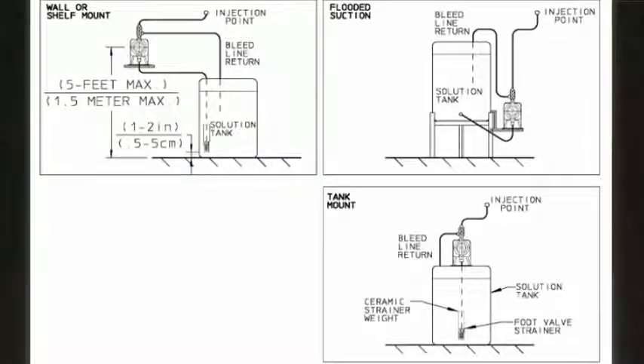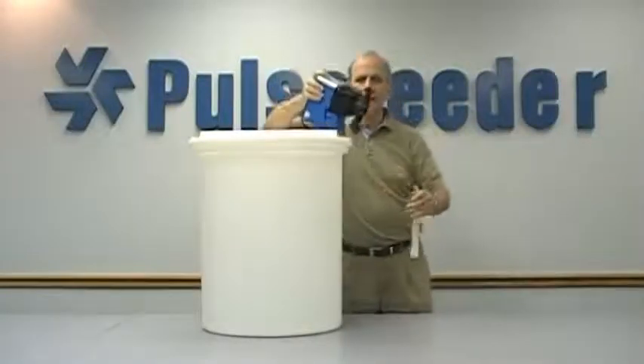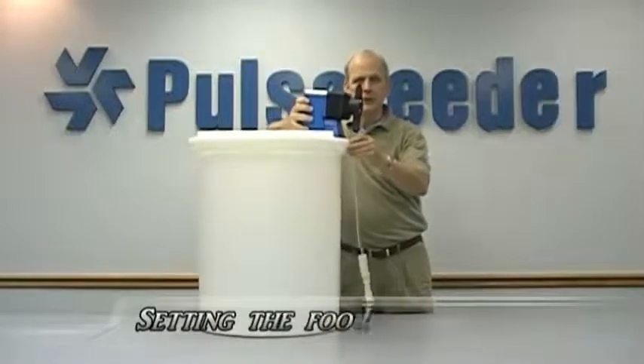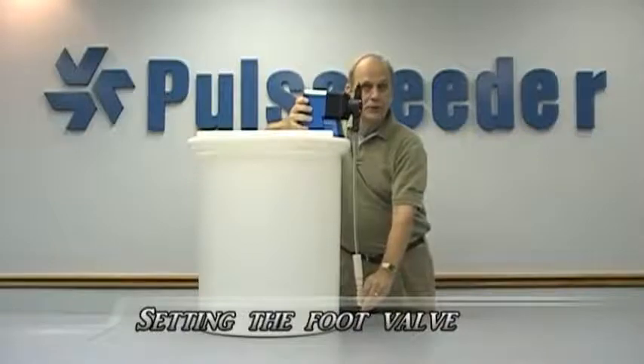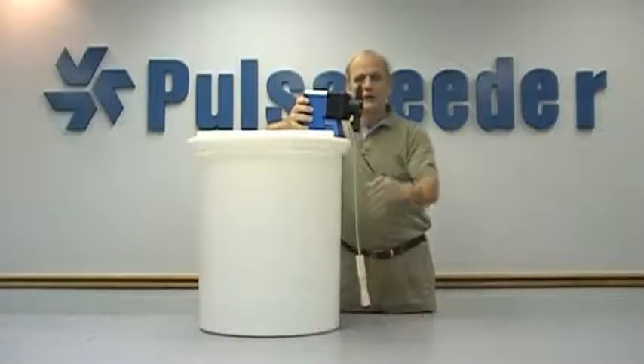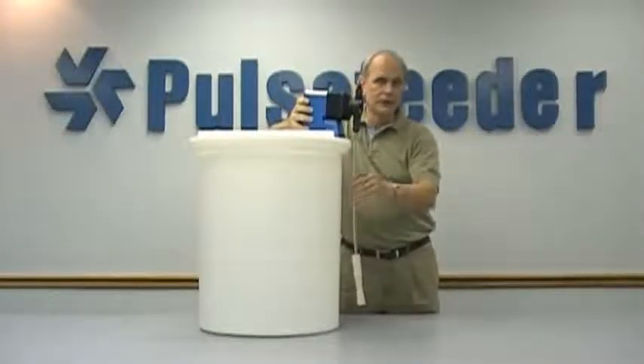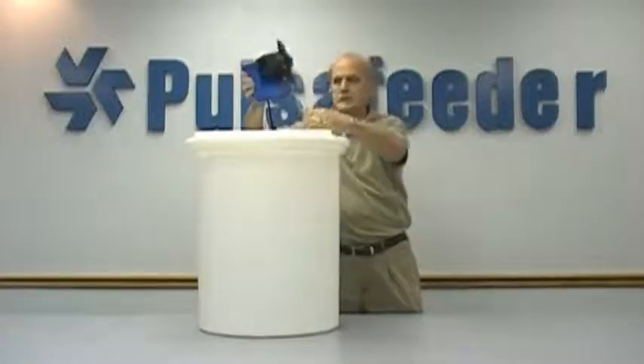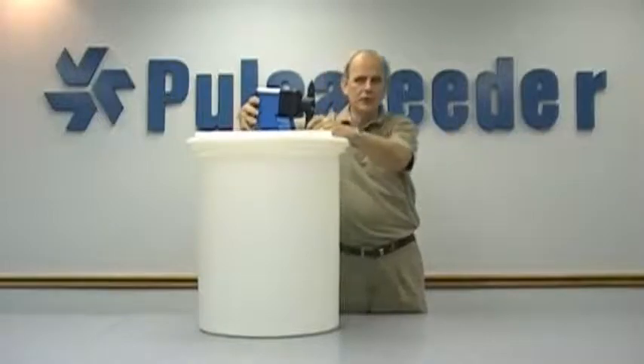A flooded suction or tank mount installation is preferred. For optimum performance, the distance from the pump head and the lowest possible fluid level in the supply tank must not exceed 5 feet. The injection point must be higher than the top of the solution supply tank to prohibit gravity feeding. Installation of an anti-siphon valve will prevent this from occurring. As we indicated earlier, the suction tubing needs to be trimmed so that the strainer is 1 or 2 inches above the bottom of the tank. This will prevent premature clogging of the strainer. Now you are ready to mount your pump on your tank.